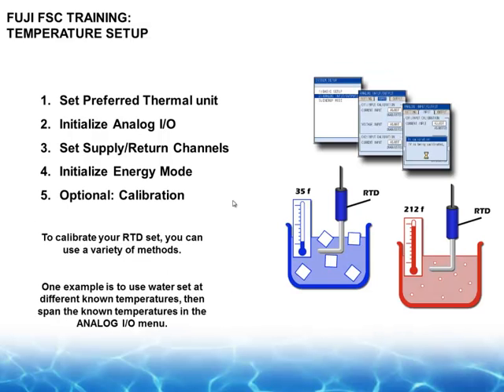And so as I said, the hardware is calibrated. You put it on a pipe as I just mentioned there, and you're done. And the logger is all set to go to accept the data. Should you have to use somebody else's temperature sensors, you do have the ability to calibrate for it. You won't get the degree of accuracies if you use somebody else's temperature sensors than our kit.